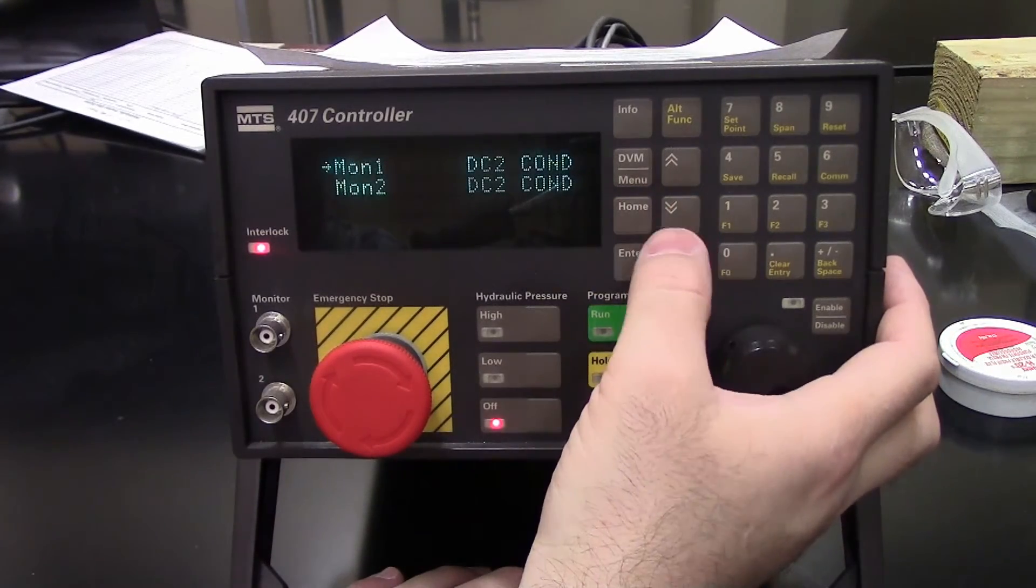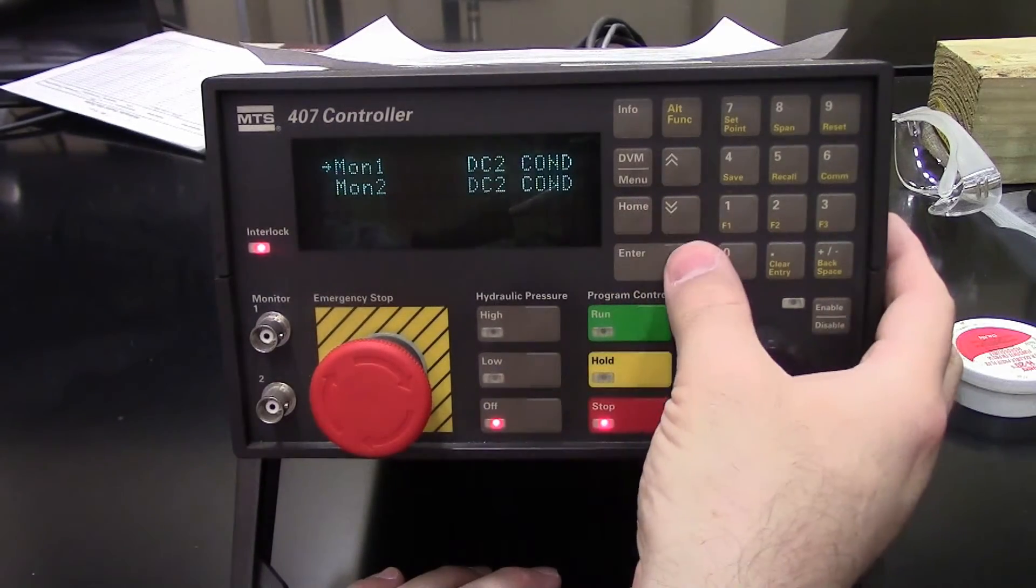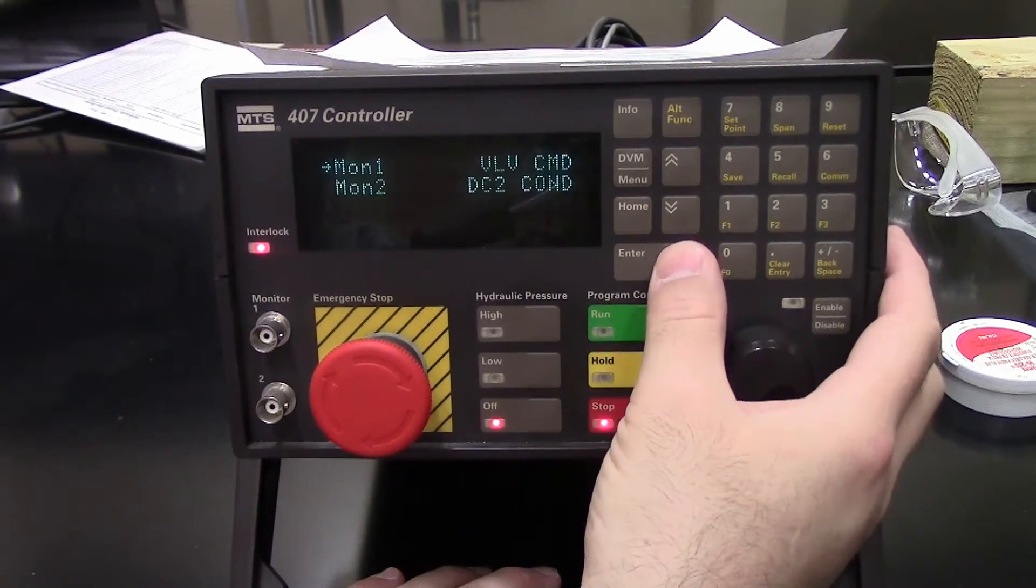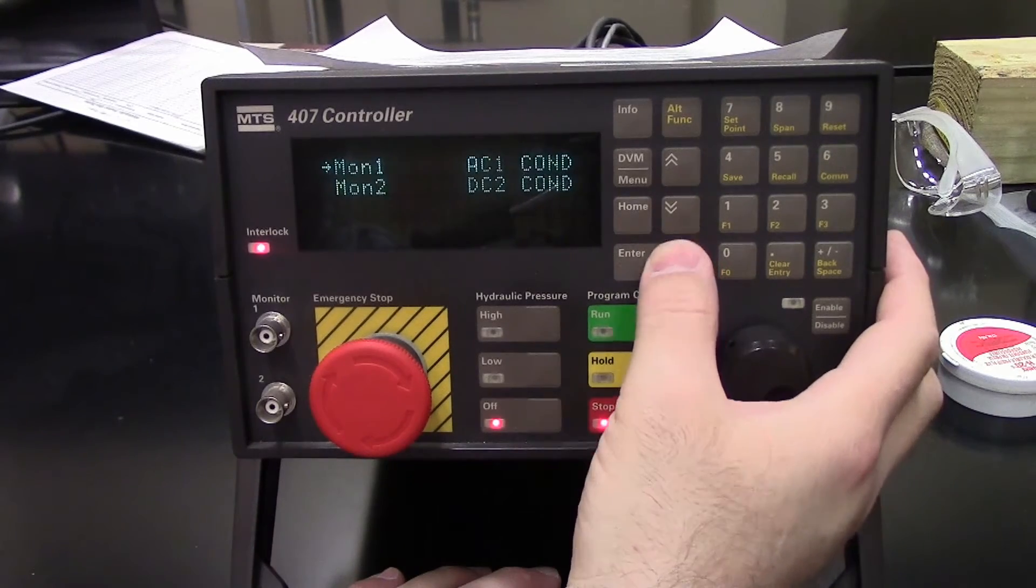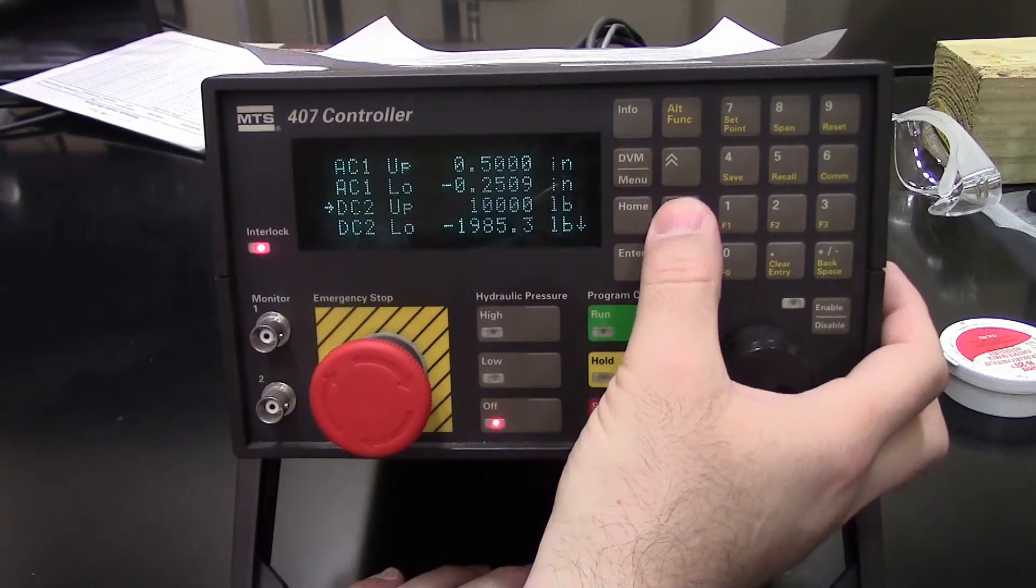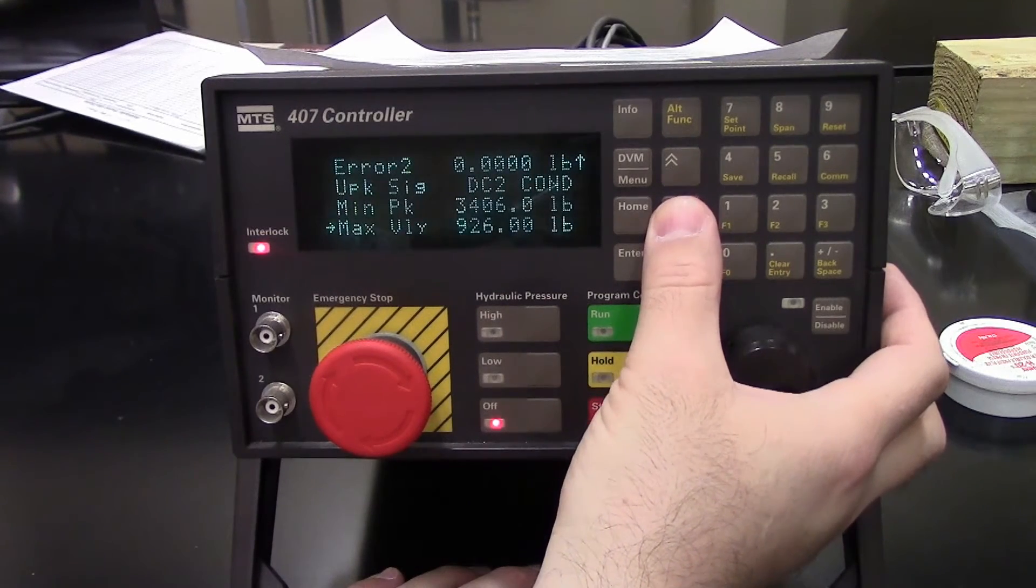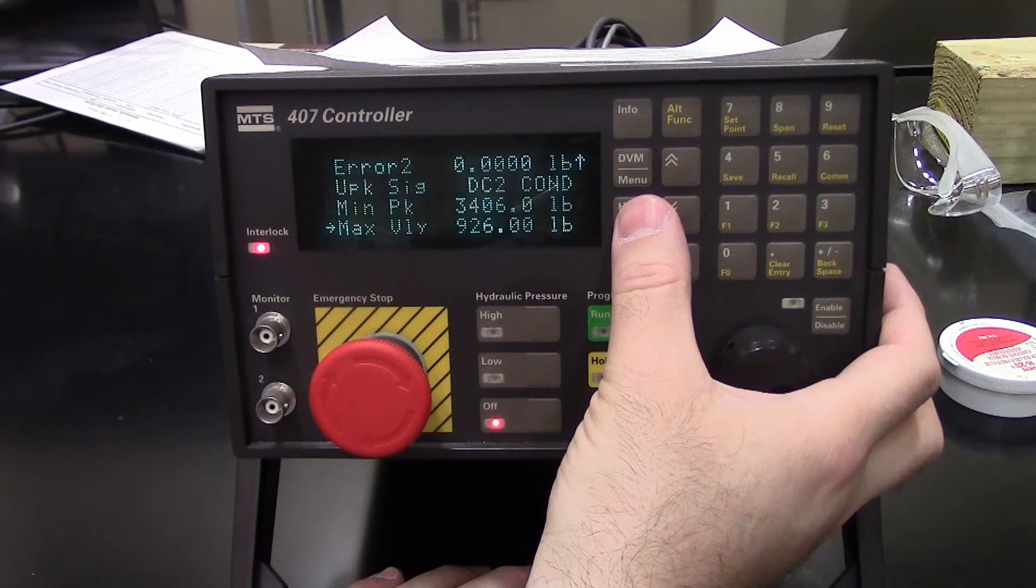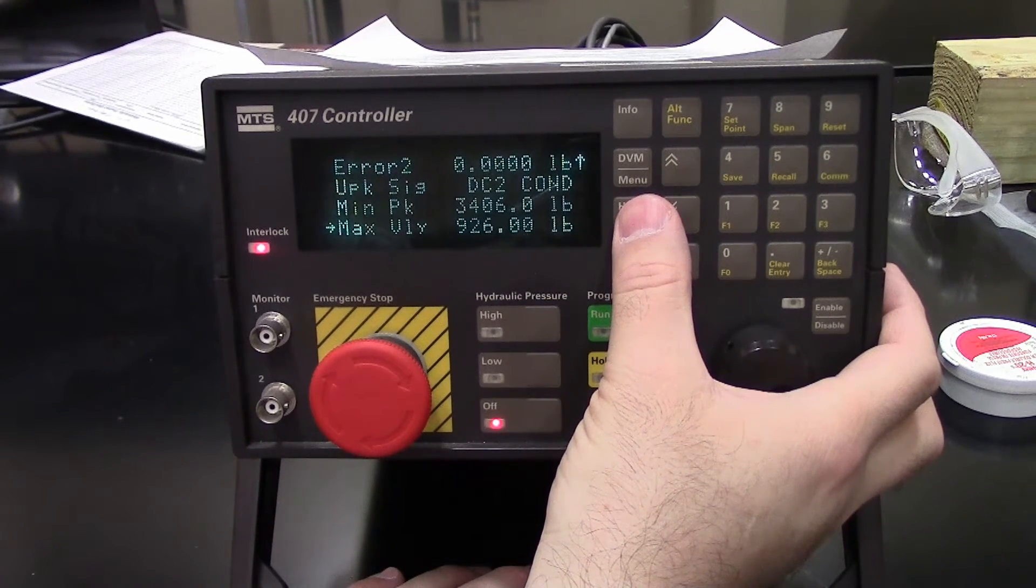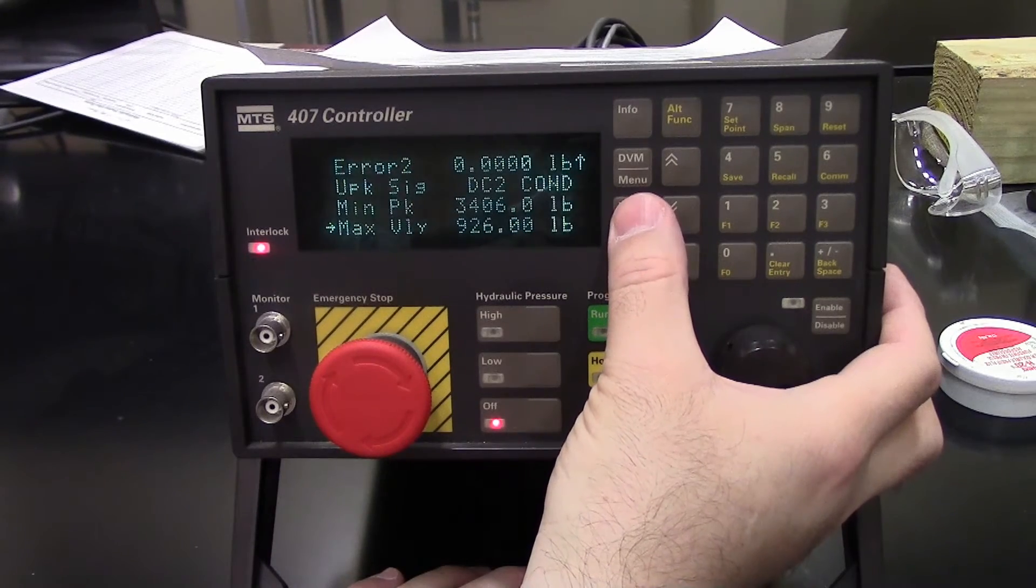Monitor select. This is where you can select the outputs for the B and C connections. Command signal, error signal, and so forth. Limit levels. Those would depend on your test. Minimum peak and maximum valley depend on whether or not you have amplitude control installed.